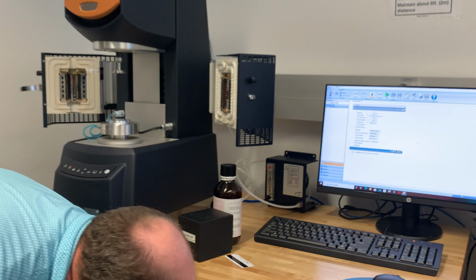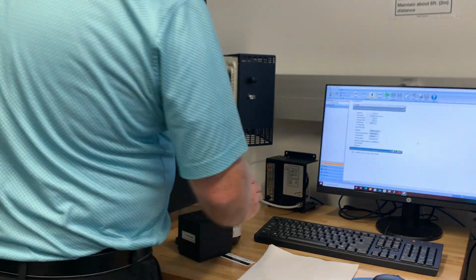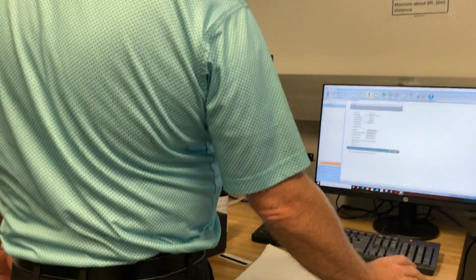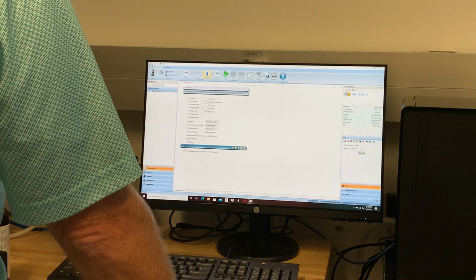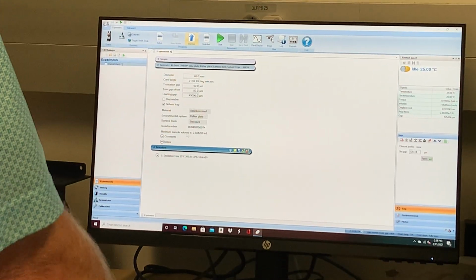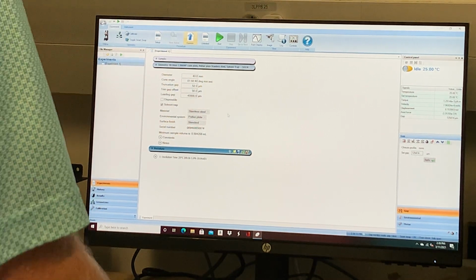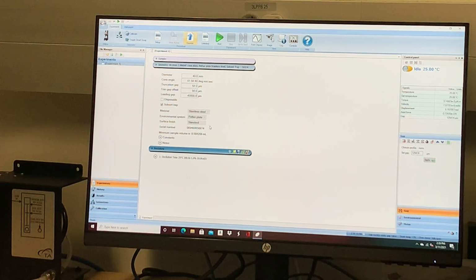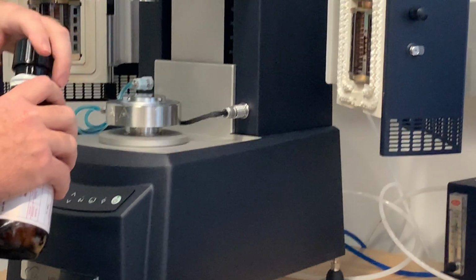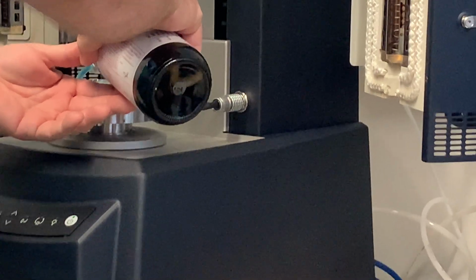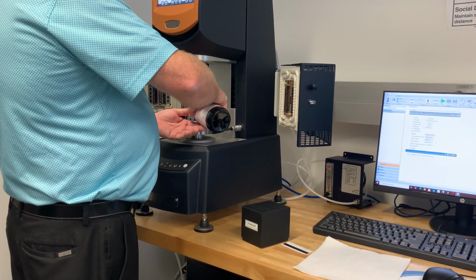If we look at the geometry settings, with a 40 millimeter 2-degree cone with a 52 micron truncation gap, these settings give you a minimum sample volume right here. So 0.58 mil, 0.6 mil, which is important for rheology. You want to make sure you have at least 0.6 mil there. I am just going to pour some on the plate because I've got a pretty good eye.